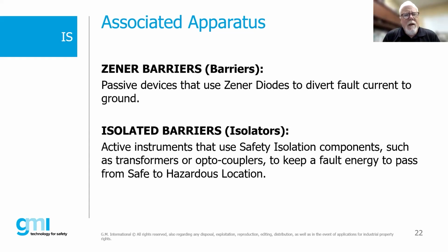The important thing to note here is that we divert that fault current to ground. So therefore, a requirement for Zener barriers is that we have ground. Now, in some cases, that's typically the biggest issue that we really run into with the use of Zener barriers. In many applications, we don't have a good isolated ground, if you will, and it makes it somewhat difficult to use those. And quite honestly, that was the reason why the isolated barriers were developed.